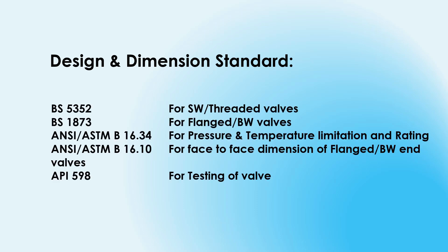Design and dimension standards: BS 5352 for socket-weld and threaded valves; BS 1873 for flanged or butt-weld valves; ANSI/ASME B16.34 for pressure and temperature limitations and ratings; ANSI/ASME B16.10 for face-to-face dimensions of flanged and butt-weld end valves; API 598 for testing of valves.